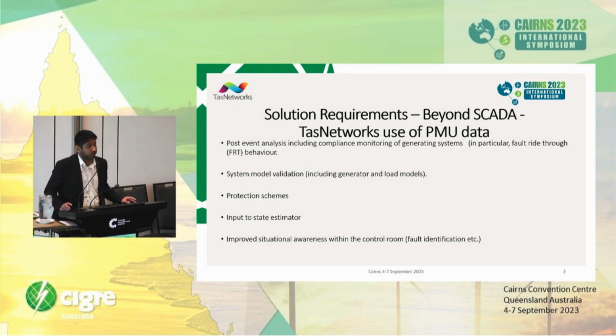This is a software. It takes data from the PMUs you have available, and it also takes the voltages you have from conventional sources. It conditions them and derives more accurate voltages for us. This has already been explained by a few speakers before, so that's one of the most common applications as well. Apart from that, it helps us analyze faults and post-fault behavior, and also do system model validation.